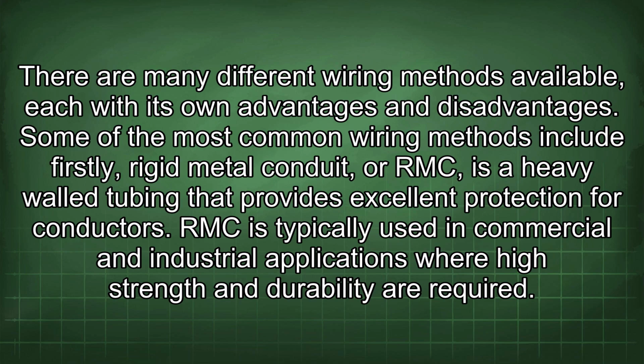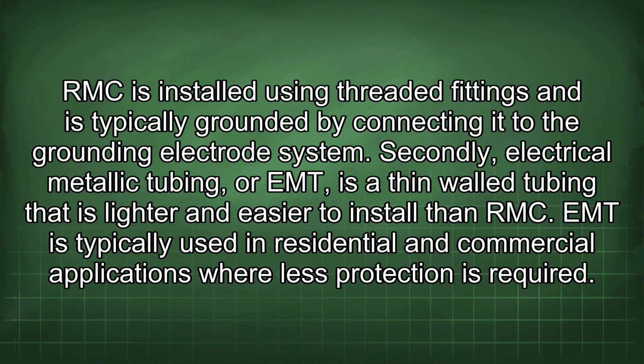provides excellent protection for conductors. RMC is typically used in commercial and industrial applications where high strength and durability are required. RMC is installed using threaded fittings and is typically grounded by connecting it to the grounding electrode system.